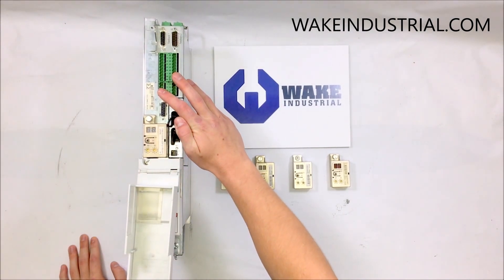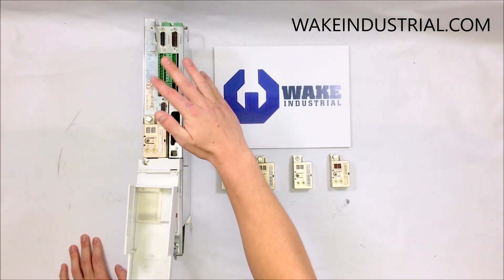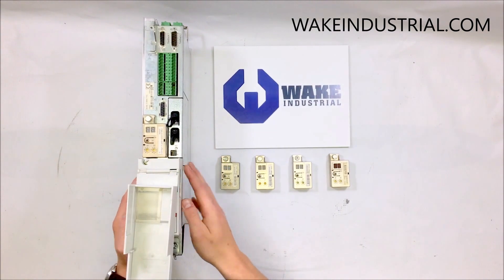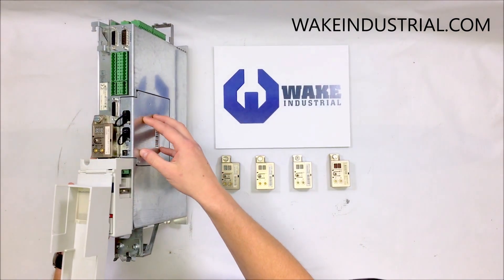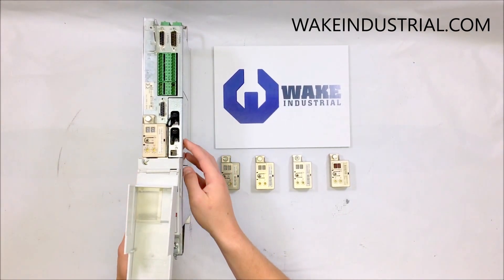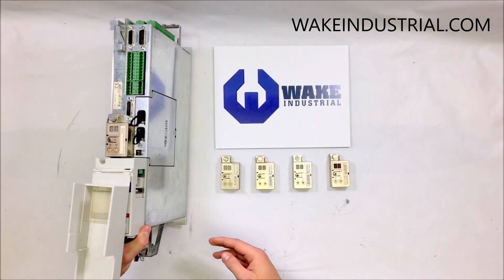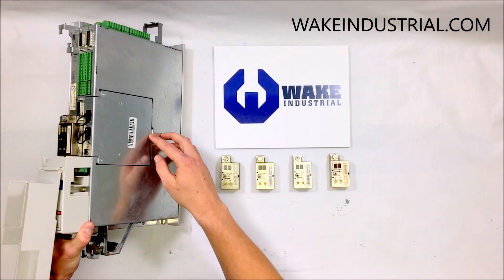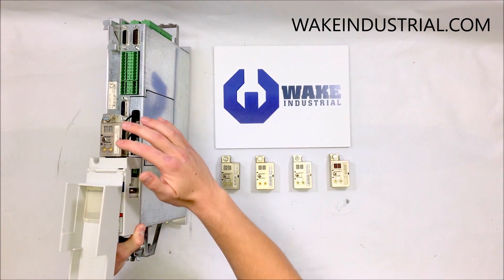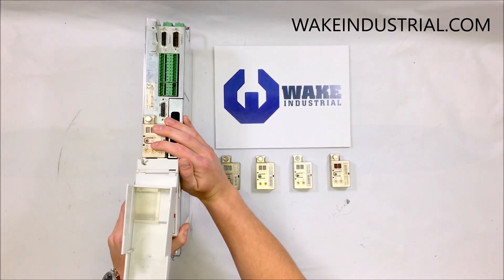All the 40 amp drives look pretty much the same, as do all the 100 amp, 200 amp, and 16 amp drives. The only thing that really differentiates them is the option card found on the side and the encoder, which has to be matched to that option card. The option card on the side can be removed by removing these three screws and then putting whatever option card back on with the correct encoder to match.